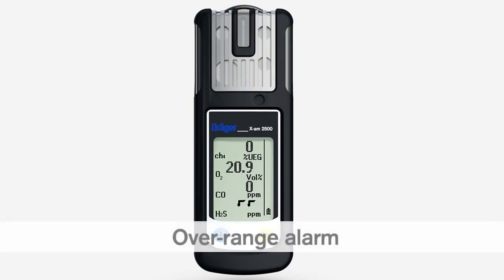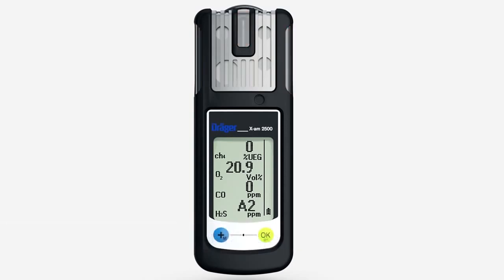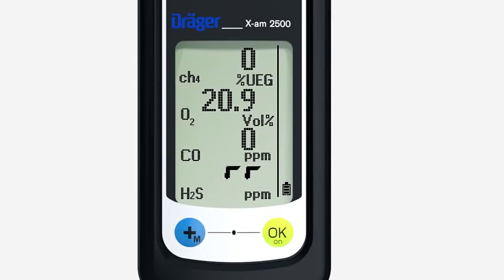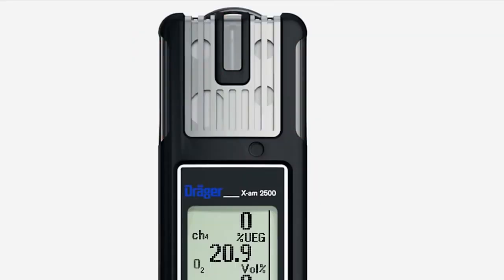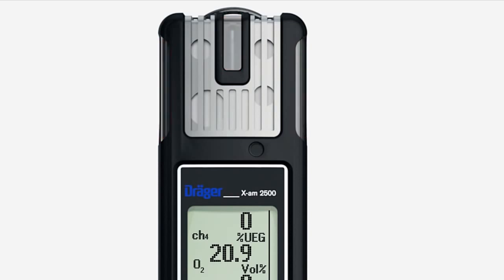An overrange alarm, indicating that the measuring range has been exceeded, is signaled by the audible, visual and vibration alarms. In addition, this symbol alternates in the display with the A2 main alarm symbol. The ambient air contains concentrations exceeding the measuring range of the sensor used. Leave the danger zone immediately. This alarm cannot be acknowledged.